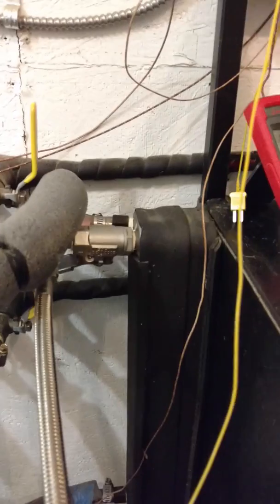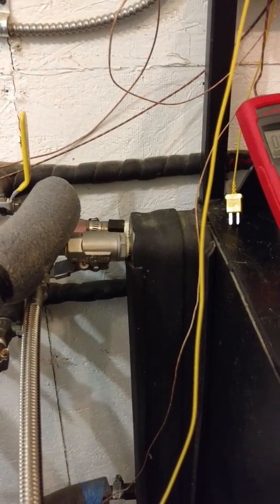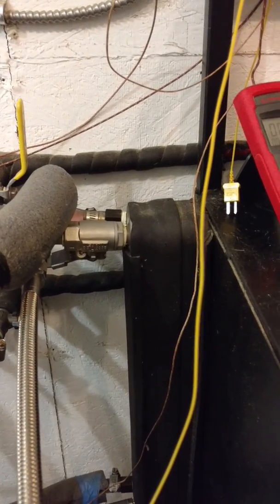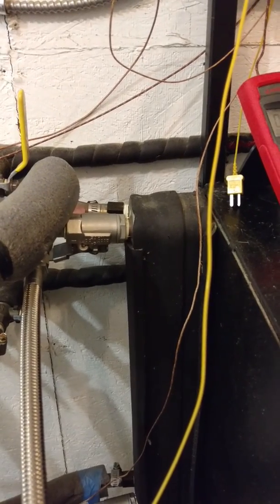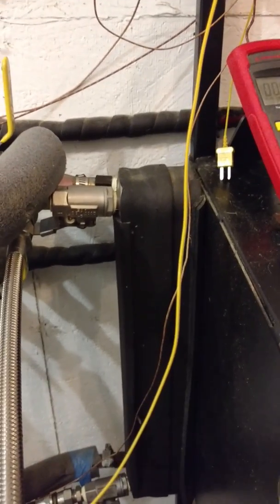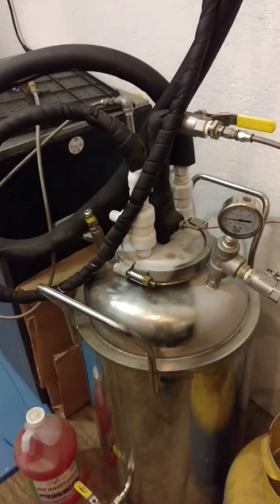This here is a flat plate heat exchanger that we're running with a little homemade chiller. It's kind of a secondary condenser, actually the first condenser off the compressor, but it runs through this flat plate and then onto the tank, where we recover it.